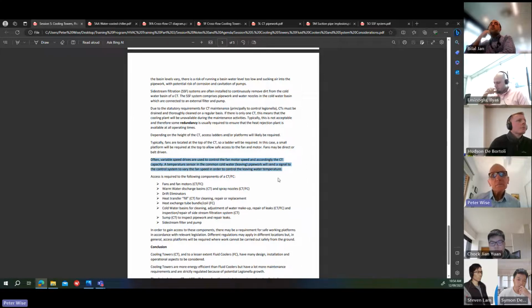And you get energy efficiency, energy savings. You can reduce the airflow at times when the ambient conditions are suitable to save fan energy and still maintain the condenser water temperature that you want.